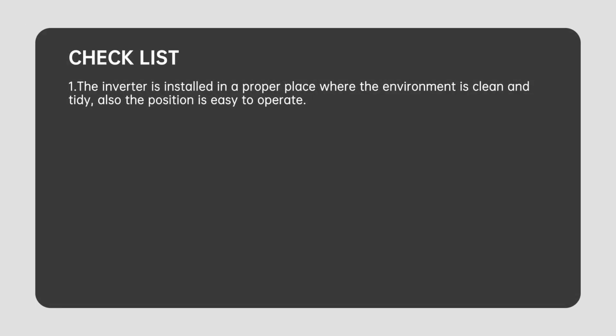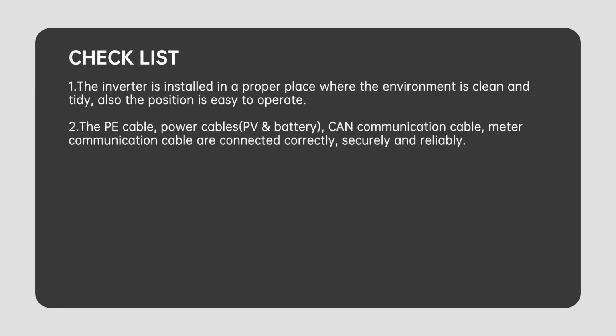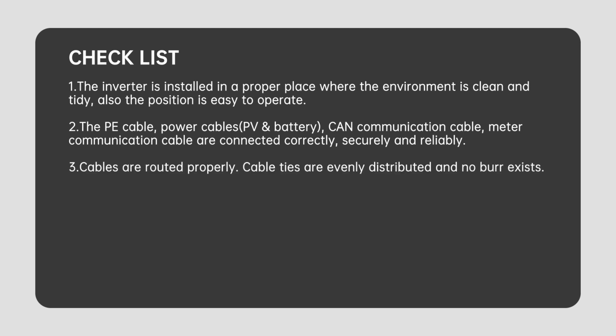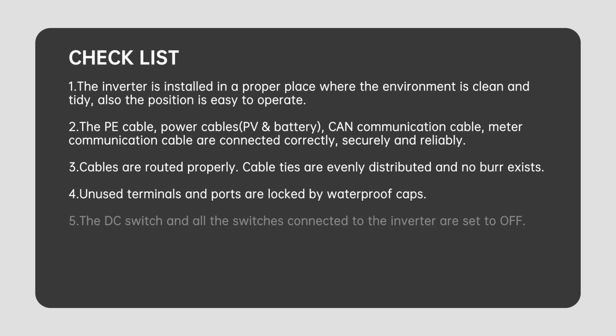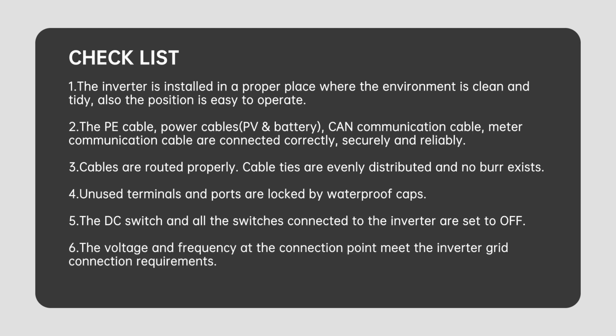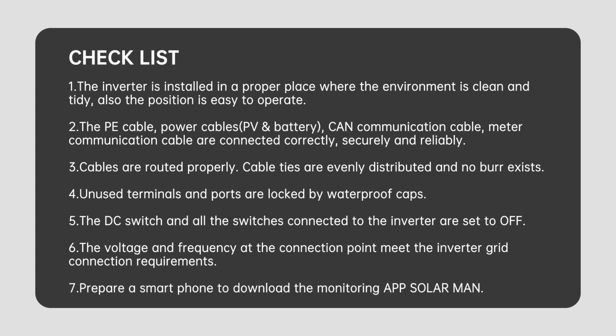Please check the following items before power on. The inverter is installed in a proper place where the environment is clean and tidy. Also, the position is easy to operate. The PE cable, power cables, communication cable, meter communication cable are connected correctly, securely, and reliably. Cables are routed properly. Cable ties are evenly distributed, and no burr exists. Unused terminals and ports are locked by waterproof caps. The DC switch and all the switches connected to the inverter are set to off. The voltage and frequency at the connection point meet the inverter grid connection requirements. Prepare a smartphone to download the monitoring app, SolarMan.